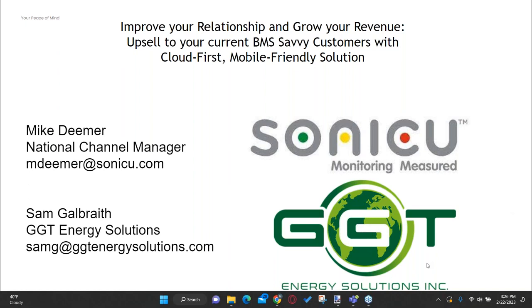You guys talked about compliance, and your sensors are going to be installed into these hospitals to help them become compliant. Do you have any kind of alerts for when they need to be recalibrated, so the BMS system knows that sensor needs recalibration at a certain time to stay in compliance? A hundred percent. All the sensors Sonicu manufactures come with a 1 or 2 year NIST calibration certificate.